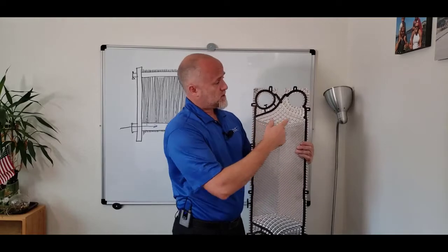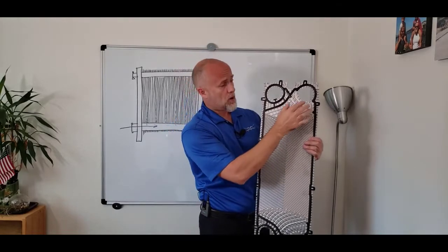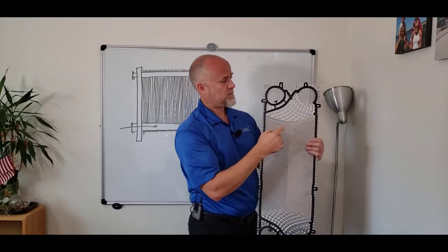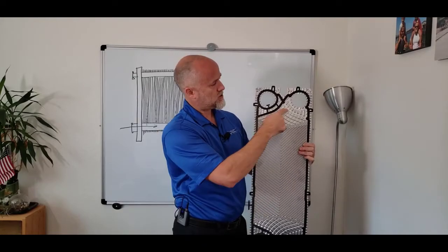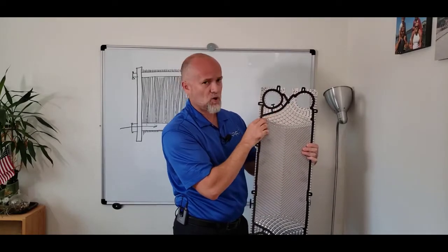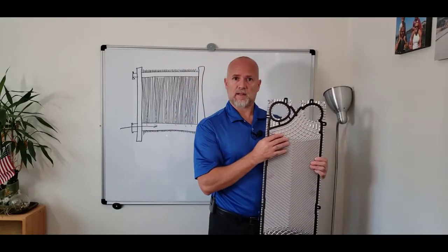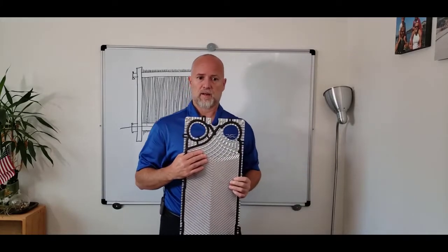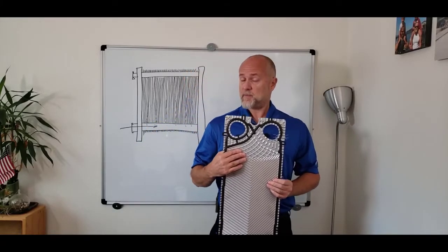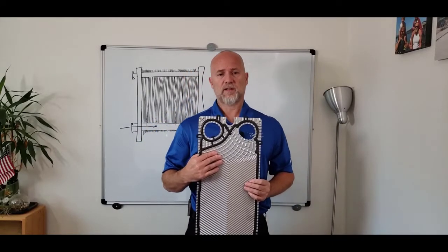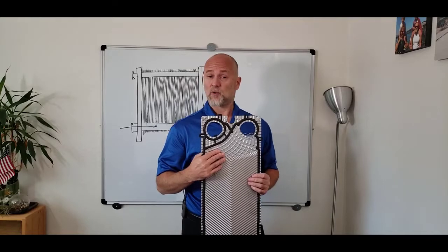And a key aspect, of course, is you want to have a pressure drop of this path which is as equal as possible to the pressure drop of this path, so you don't have a path of less resistance and cold spots or hot spots that increase the chances of fouling. And this is exactly what this design does, and it has been proved that the increase in efficiency is actually significant, up to 25–30%, which is amazing if you think about that.